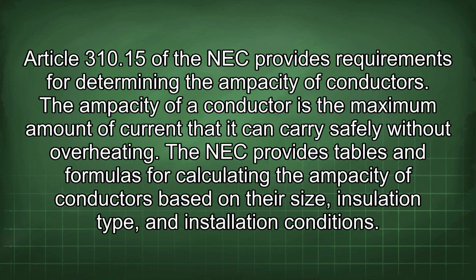Article 310.15 of the NEC provides requirements for determining the ampacity of conductors. The ampacity of a conductor is the maximum amount of current that it can carry safely without overheating. The NEC provides tables and formulas for calculating the ampacity of conductors based on their size, insulation type, and installation conditions.